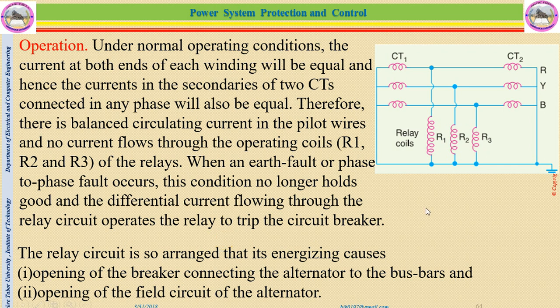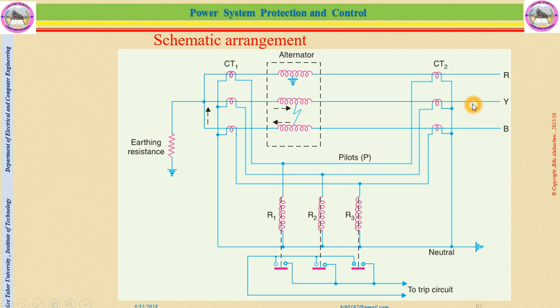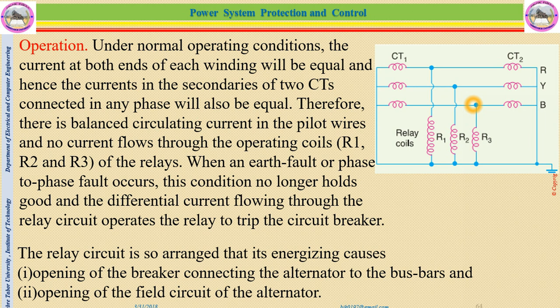Let me show it in a simplified manner. This is a simplified version of the previous diagram. So, under normal operating condition, the current at both ends of each winding will be equal. This one and this one are equal, and hence the currents in the secondaries of the CTs connected in phase will also be equal. You can see here that the two CTs, CT1 and CT2, are equal.